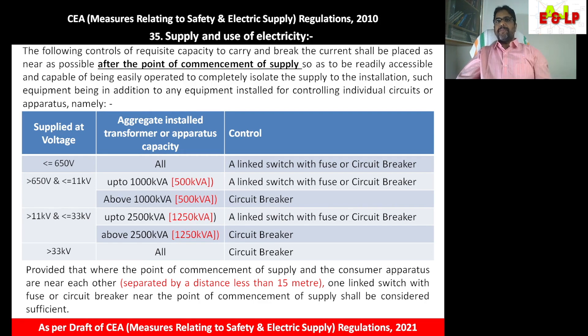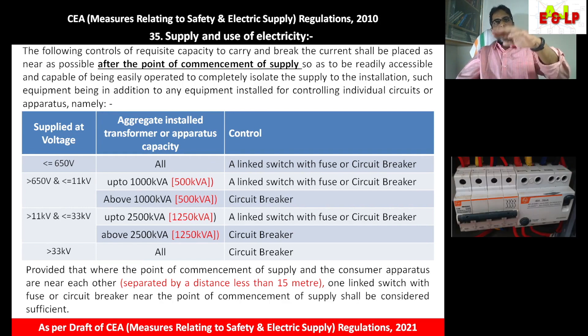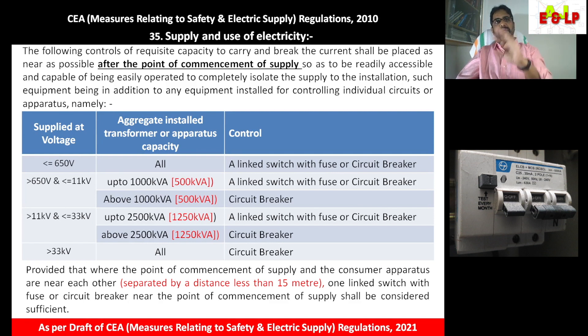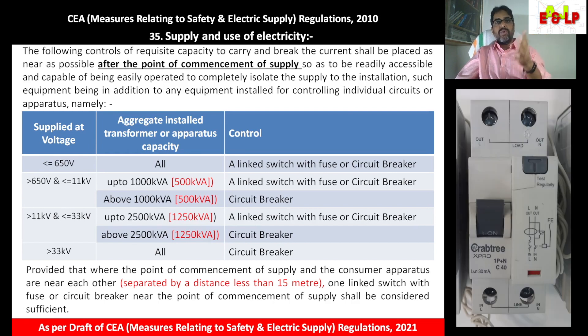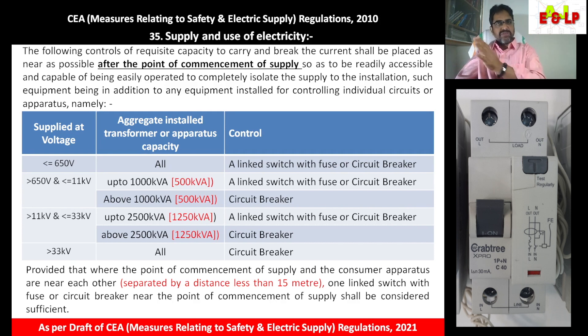If it is an MCB, we can club it with an RCCB, making it an RCBO. Many licensees are insisting consumers provide an RCCB visible near the point of commencement of supply, possibly for regular inspection. If it is for inspection, it is good; otherwise, it cannot be insisted upon because it is not stated in the regulation. As per Regulation 42, all consumers should provide an RCCB. But if there are many distribution boards, it is not necessary to keep the RCCB near the main switch.